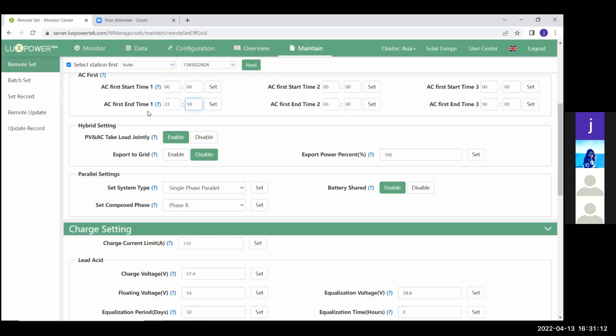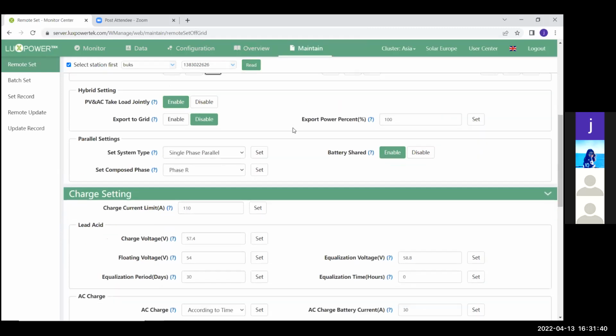Now, if the client has installed the system to save money, then we recommend you change all these values to 0000. And then if you have all your values at AC first time 1, 2, and 3 set to 00s like this, you press set next to each one, then your system will tell you it was set successfully. That means your setting has taken effect on the inverter.